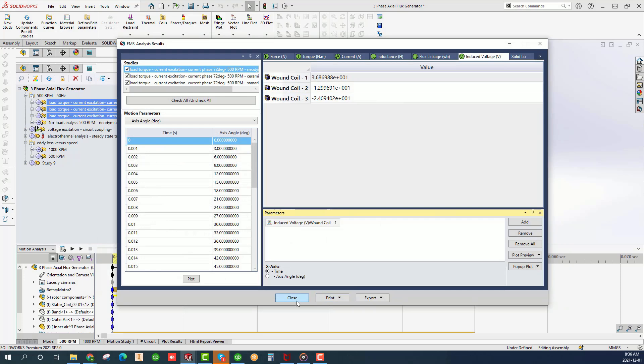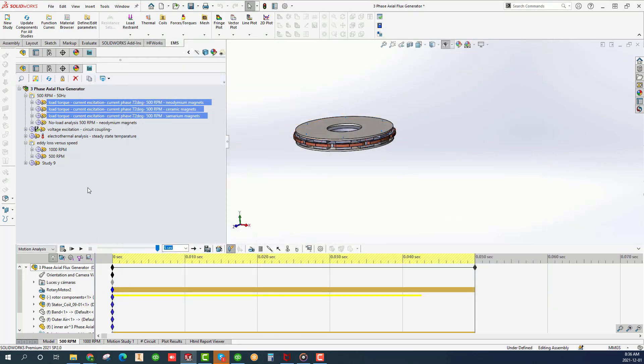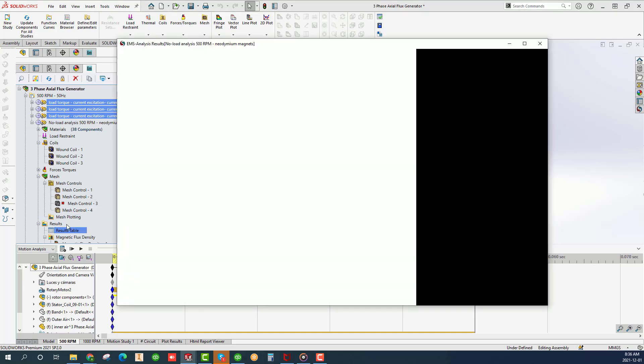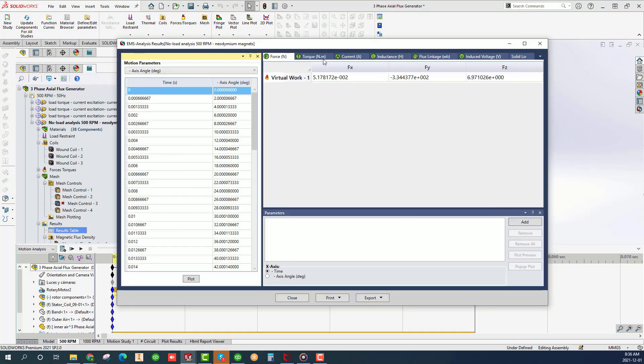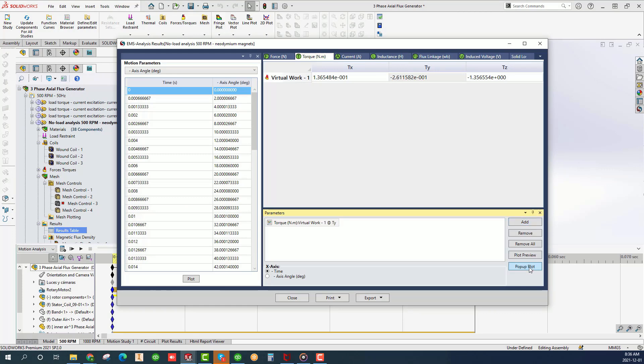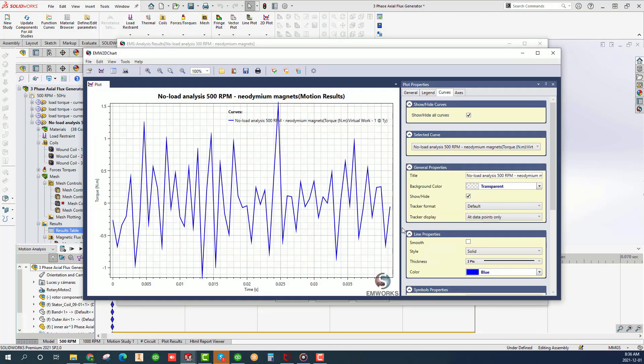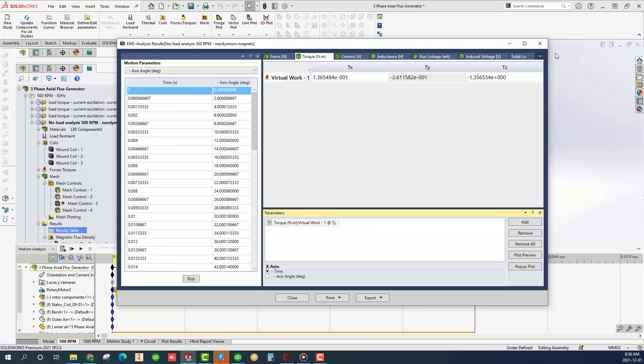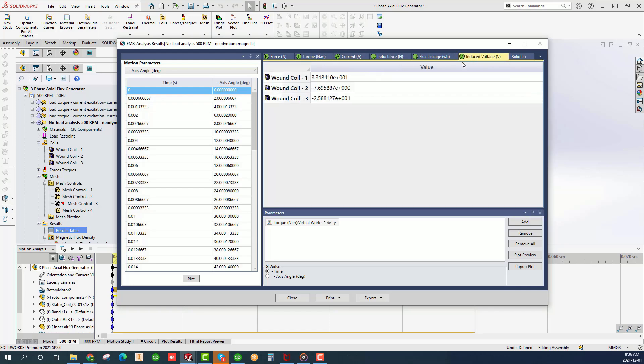Let's now examine the no load analysis. Double click on the results table and plot the TY component following the same procedure outlined earlier. Since it is a no load analysis, this torque is the cogging torque which is relatively small.